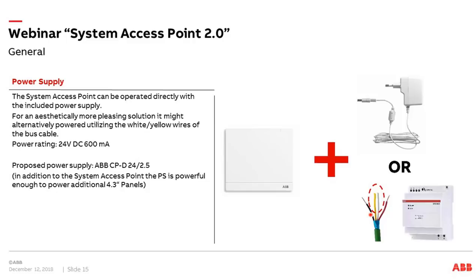In general, the system access point requires 24V. You can use the power adapter on the bottom side, or you can power it with the white and yellow wire of the bus cable — which may be the more practical solution when mounting it on a wall or in a cabinet. For that, we recommend the ABB CPD 24 power supply, which can also power additional 4.3-inch panels. This should be the preferred solution when planning a new project with wired installation.